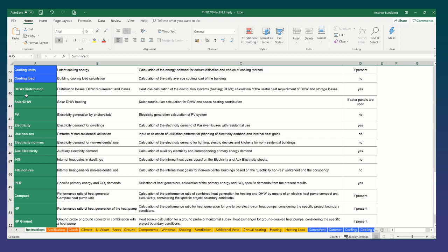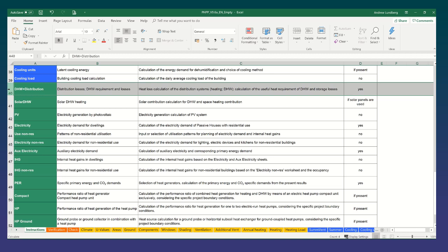Moving down then to what are plant and services sections. The domestic hot water and distribution are very important to calculating how much energy particularly primary energy basically will be required to heat the requirement of domestic hot water in the building and the distribution of that system can have a significant effect on that heat because Passive House counts basically every single runoff pipe from the cylinder to an outlet as an individual pipe because it basically calculates that once you fill a pipe with hot water that hot water will rapidly be transmitted into the dwelling around if it's running through the heated space or may even be lost to an unheated space adjacent to the building if your hot water cylinder is outside the thermal envelope which can be the case sometimes but obviously for good energy efficient building practice we try to keep all services and heating items inside the thermal envelope but it's not always practical.